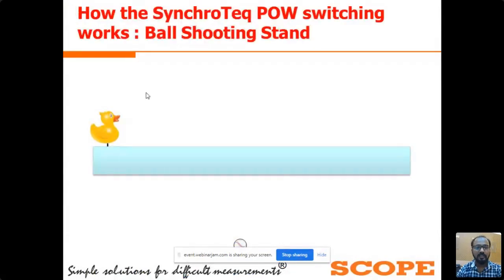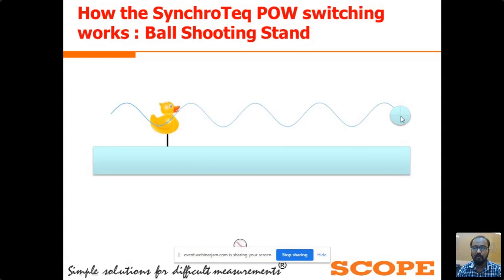Now we will see how synchronous point on wave switching works, meaning how the control switching device actually works. Here we can see by this example: consider this curve as our sinusoidal waveform, and here you can see the ball. We can consider this ball as the CB contacts. And our target is this point. We want to target this point and operate the circuit breaker. We want to hit the ball at this particular electrical target point. By this animation, we can analyze these things.